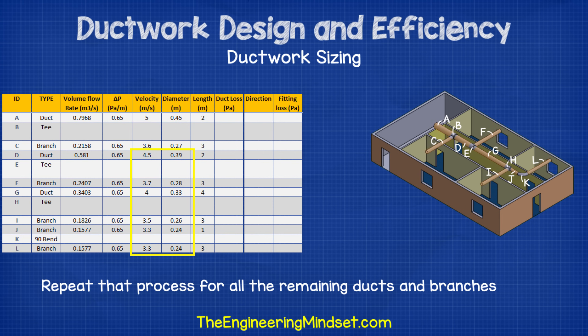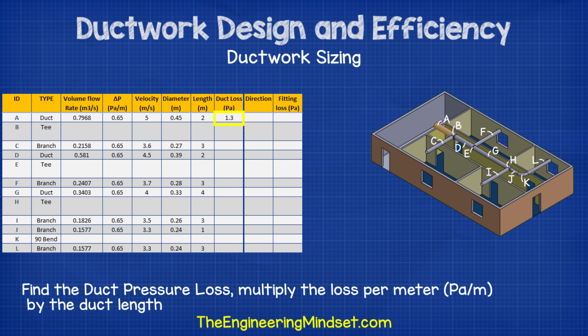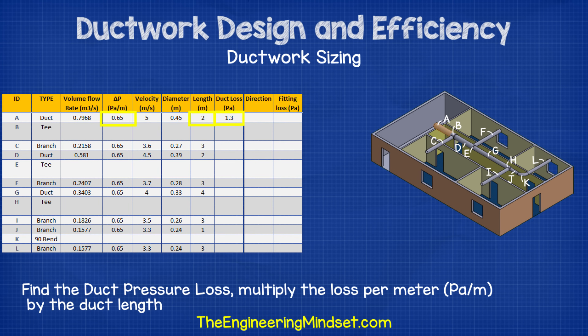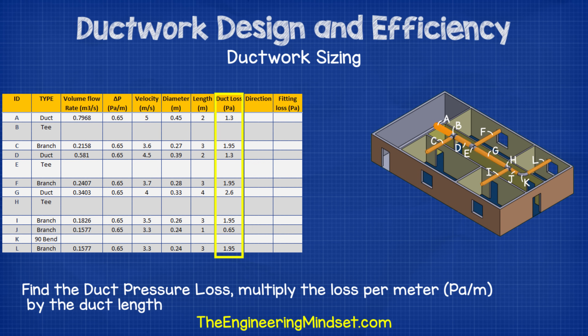Now find the total duct losses for each of the ducts and branches. It's very easy and simple to do — just multiply the duct length by the pressure drop per meter of 0.65 pascals per meter. Do that for all the ducts and branches on the table.